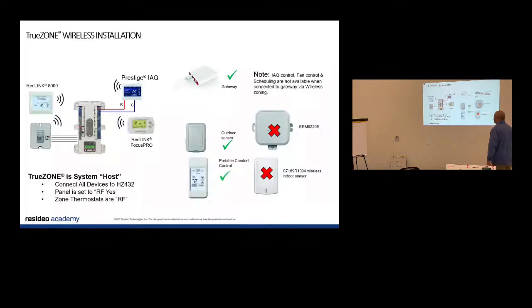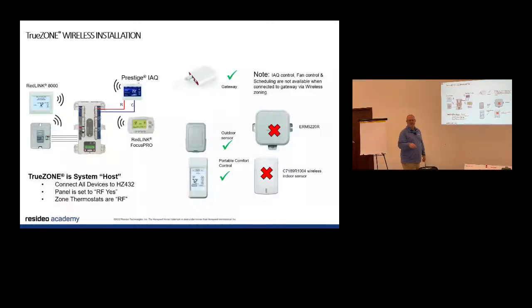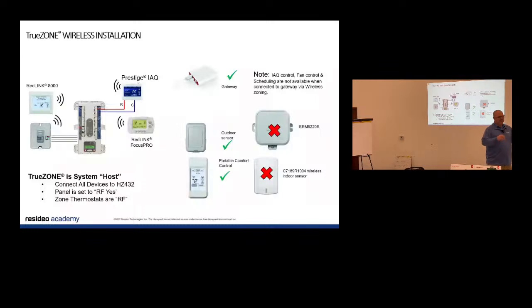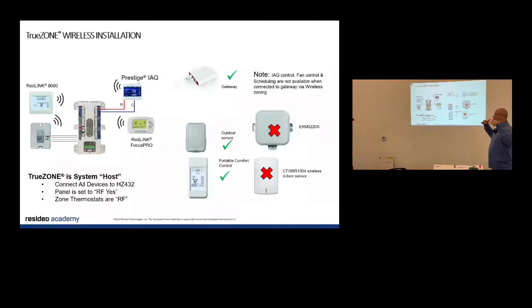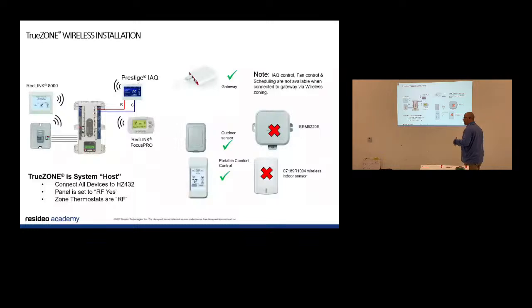Now that we have that kind of in your head, we're going to make your head spin a little bit. So, what don't we have when we do retrofit? We don't have a wire for the thermostat to the other zones, right? Because it's all finished ceilings and the basements are done, and the homeowner's saying, there's no way you're cutting into my drywall, right? But we still can get to the mechanical room. So you put the retrofit dampers in. How do you get a thermostat to that upstairs zone, or maybe to the master bedroom? We have a few ways to do it, and this is where, I wouldn't say it gets complicated, but I get this call a lot.